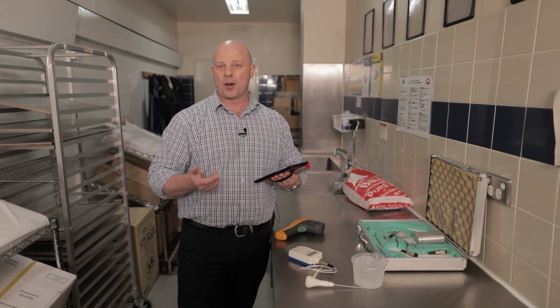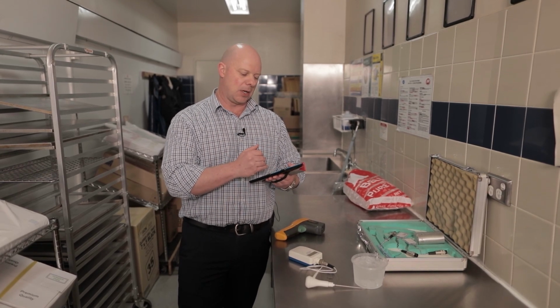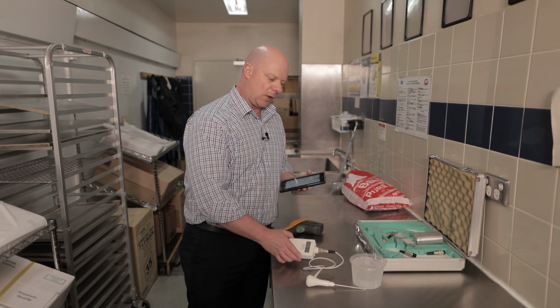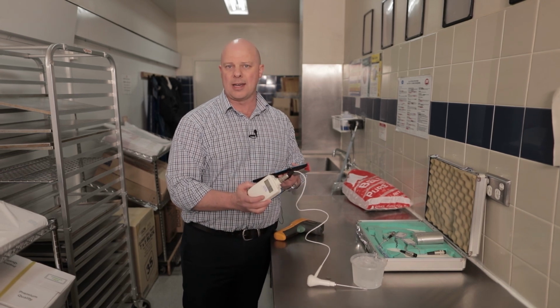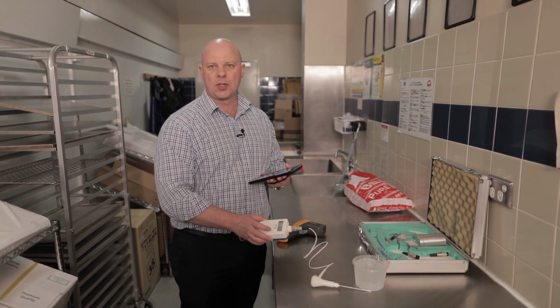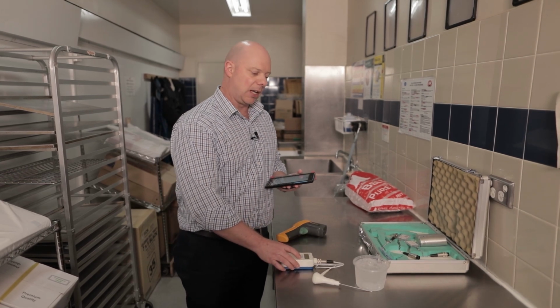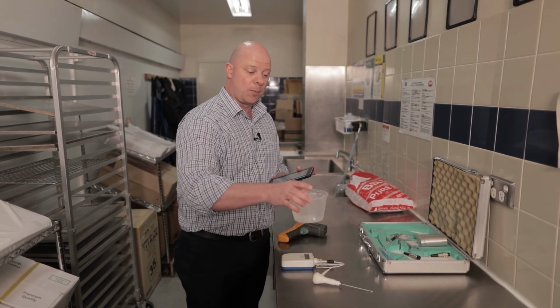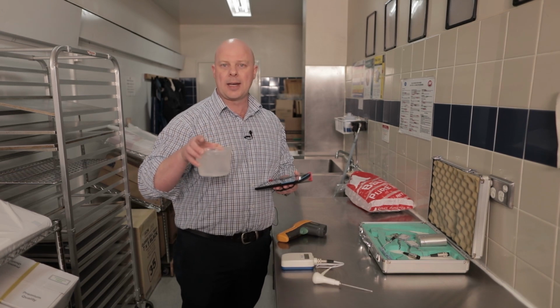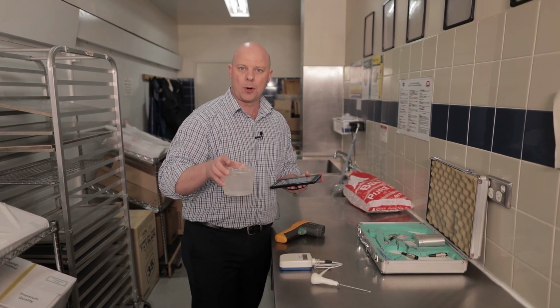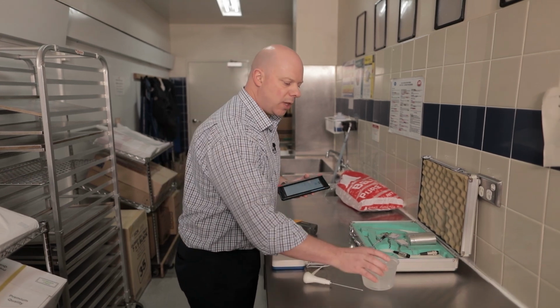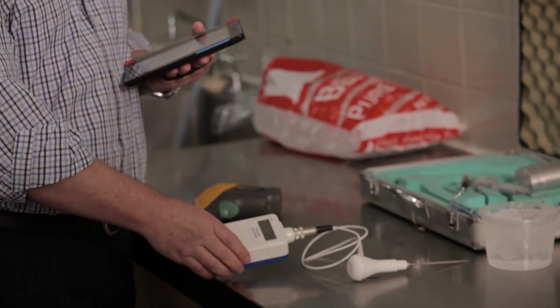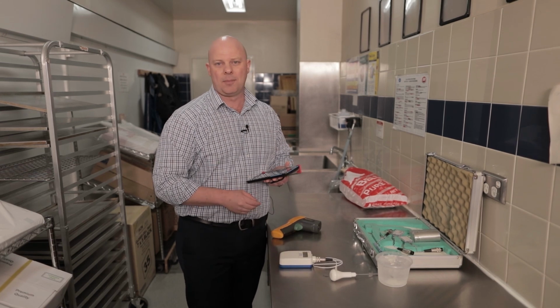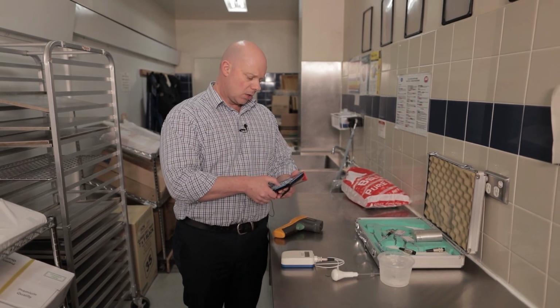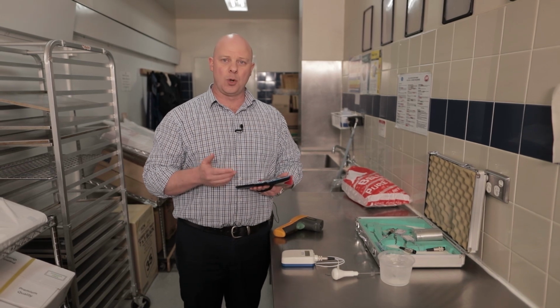If it was outside of plus or minus 1, it could be 1.1 degrees, or minus 1.1 degrees, then the tablet's going to tell you you've got a problem. That means your digital thermometer is likely not accurate. The first thing to do is change the battery and see whether that helps. The second thing, or the first, whichever order you want, is to create another ice slurry and retest the probe. One of those two things should fix the issue. If it doesn't, you will need to get a new probe, because these can't be adjusted.